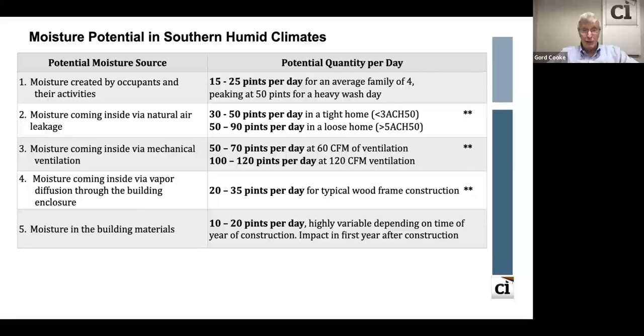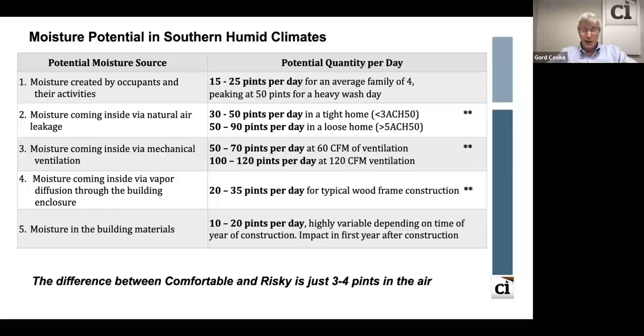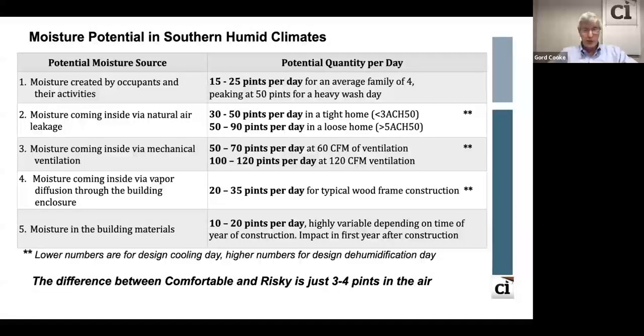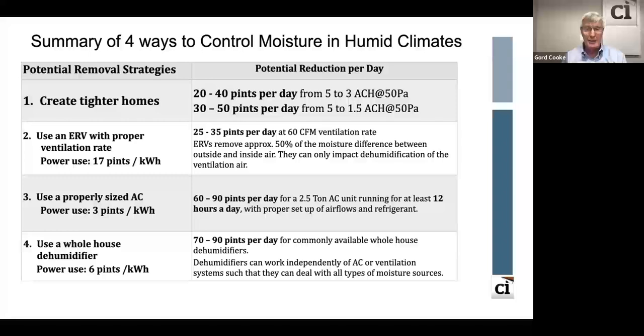And if I apply good strategies, I can reduce the risk of high levels of humidity in humid climates specifically. It doesn't have to be southern climates, but in humid climates in the summer, I can dramatically reduce the potential for humidity problems. And just as a little example of that, by creating tighter houses, by going from 5 down to 1.5, which is my recommendation, everybody should be looking at 1.5, you're reducing your humidity load by 30 to 50 pints per day. That's basically a portable dehumidifier. Not to say you don't still need a dehumidifier, because you still have other loads, but if I can get from 5 air changes down to 1.5, that's a dramatic reduction, that's pretty powerful.